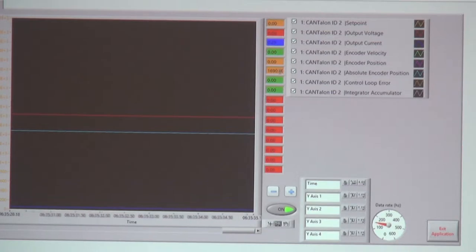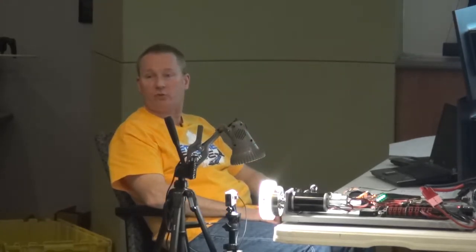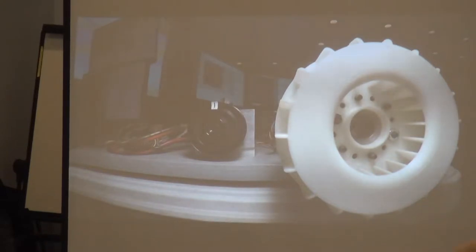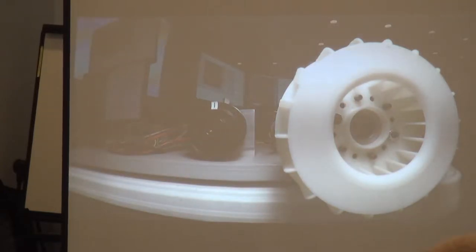If I wanted, when I fire this up I could say I want you to run that thing to wherever the absolute encoder is 1690, then zero the incremental encoder, and now zero is zero. You can manipulate all this to sort out what your zero is going to be. In position, you have to get this thing referenced — where am I starting, where am I going, how do I have values that correlate to physical things moving. Here we want to move this from zero to 360 degrees. Think of this as azimuth control, and this pulley is one-to-one with the azimuth.